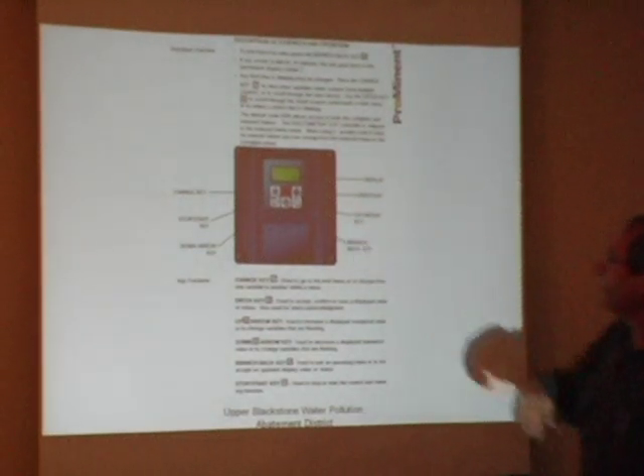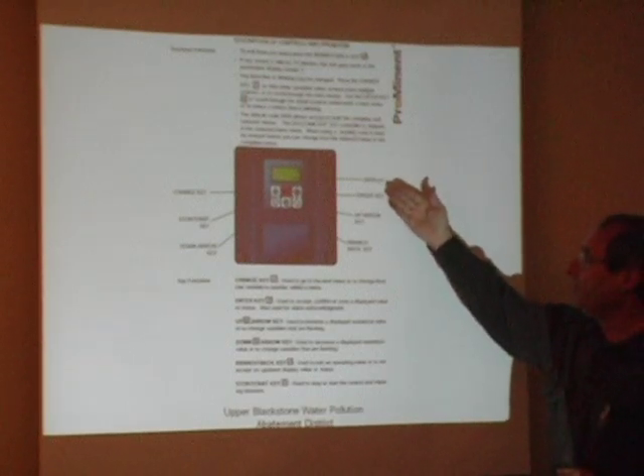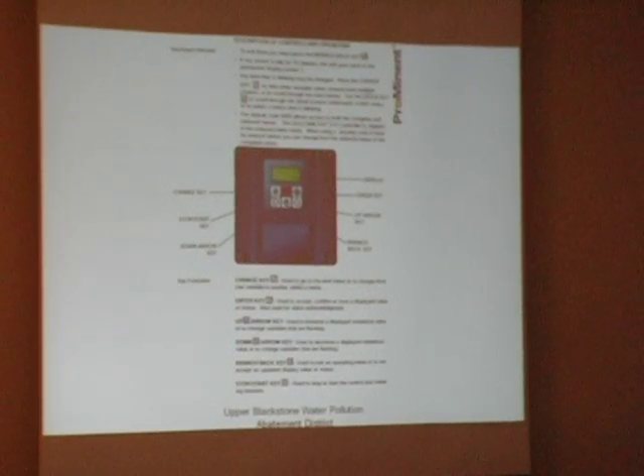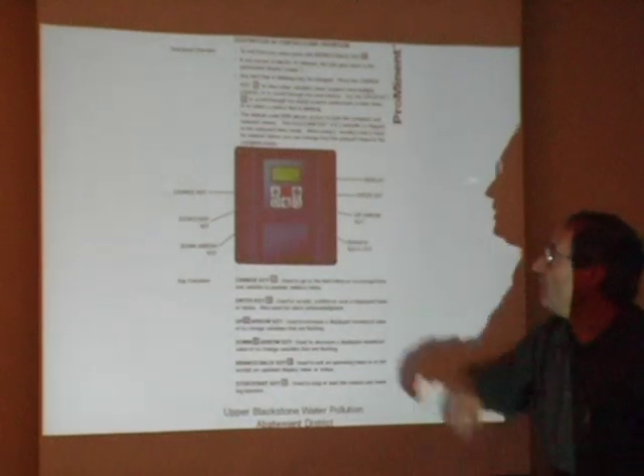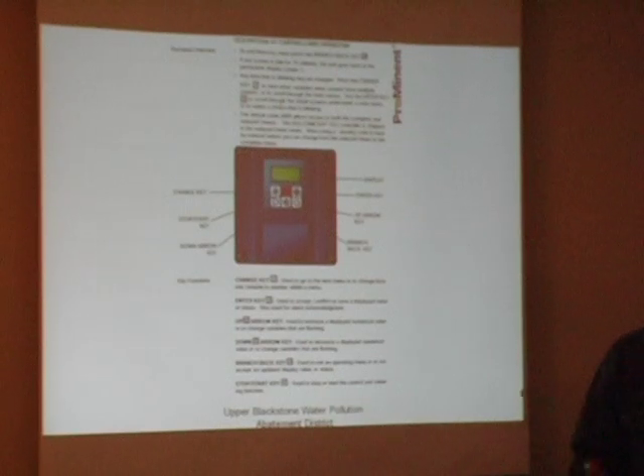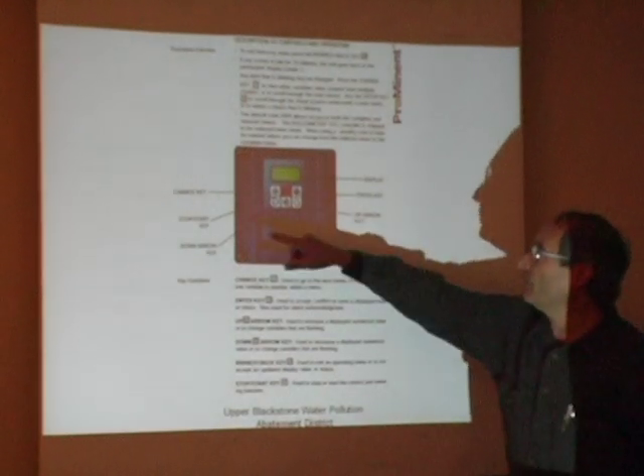This is used as an enter key to record what you have changed. If you do not press the enter key, your changes will not be registered in the instrument and you won't see any change. This key essentially moves you back up a level into your programming mode, and if you hit it, I believe, twice, it takes you right back out of the programming mode where you now are displaying your residual chlorine value. So you basically just have 4 keys that you have to deal with.